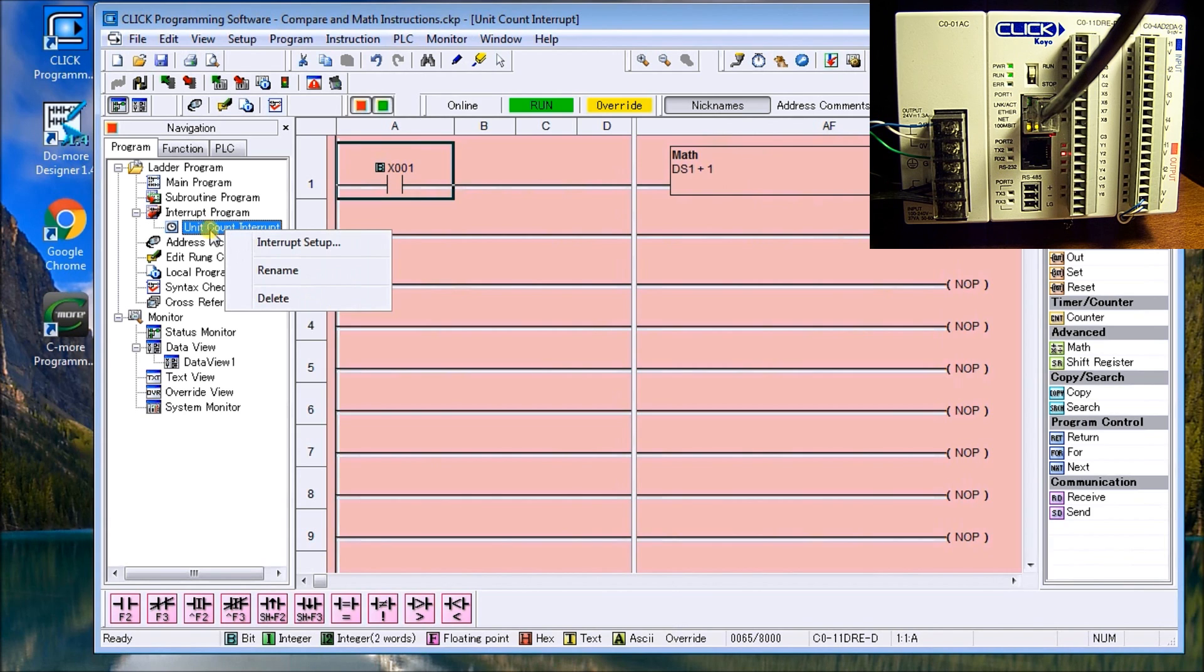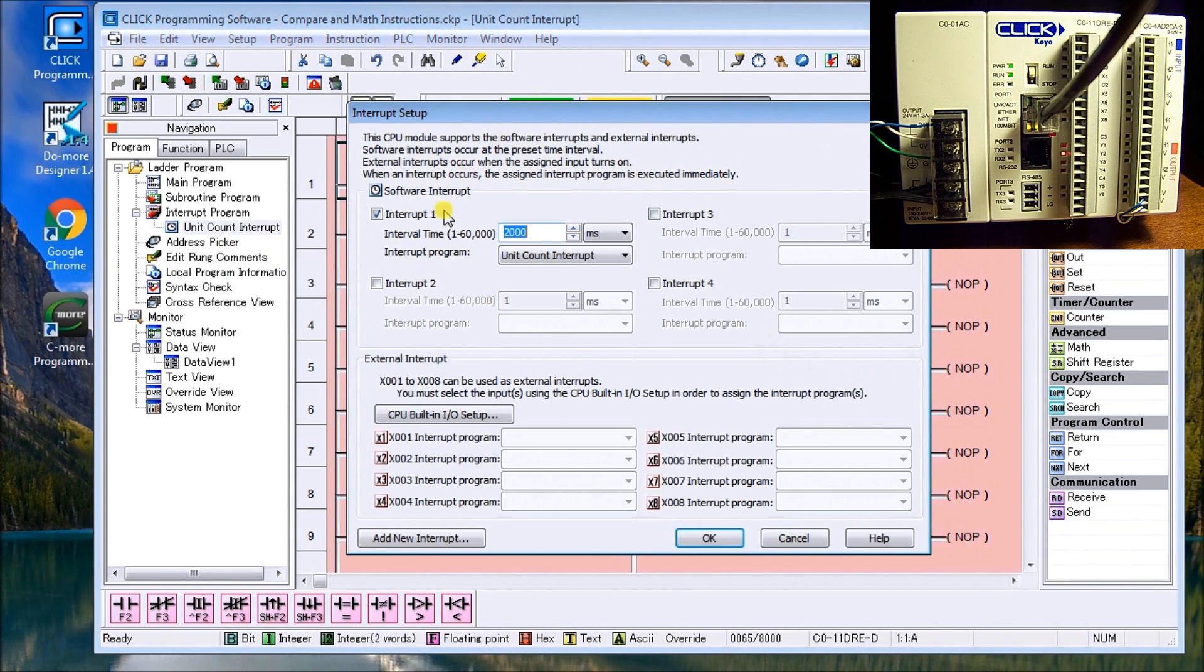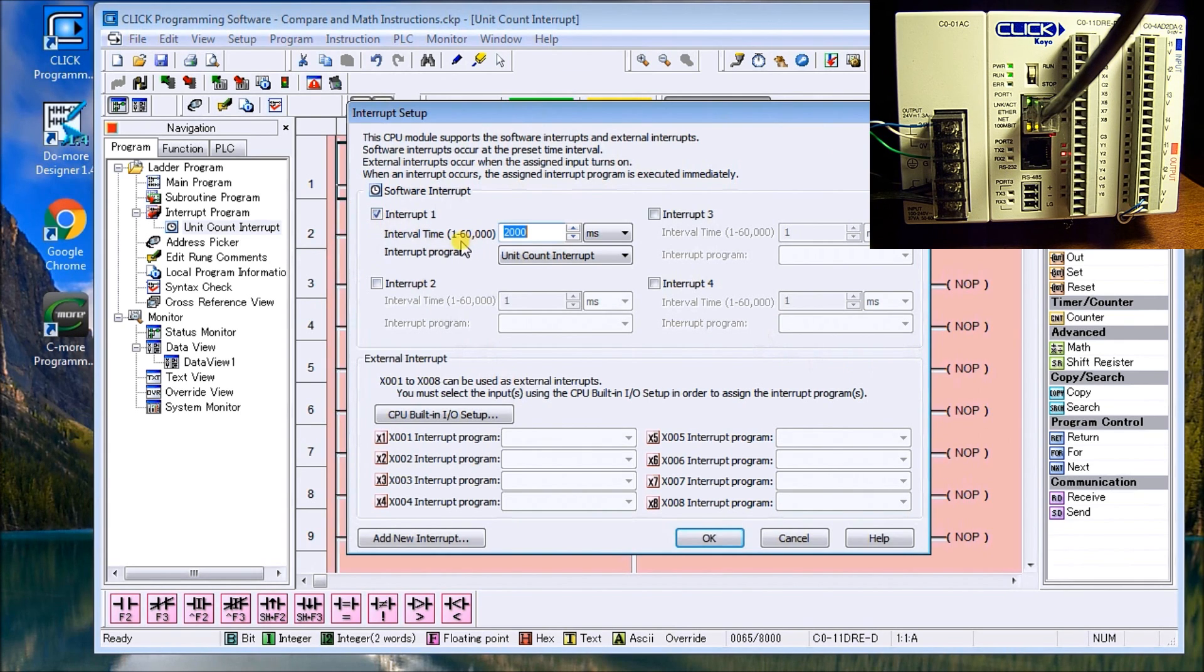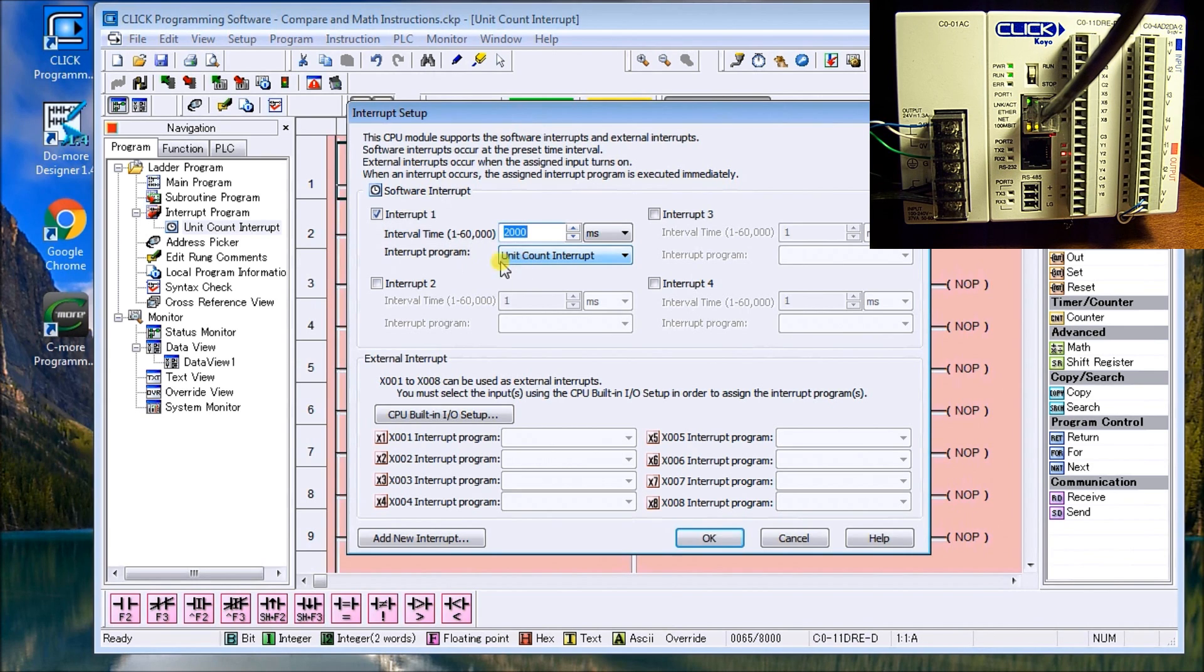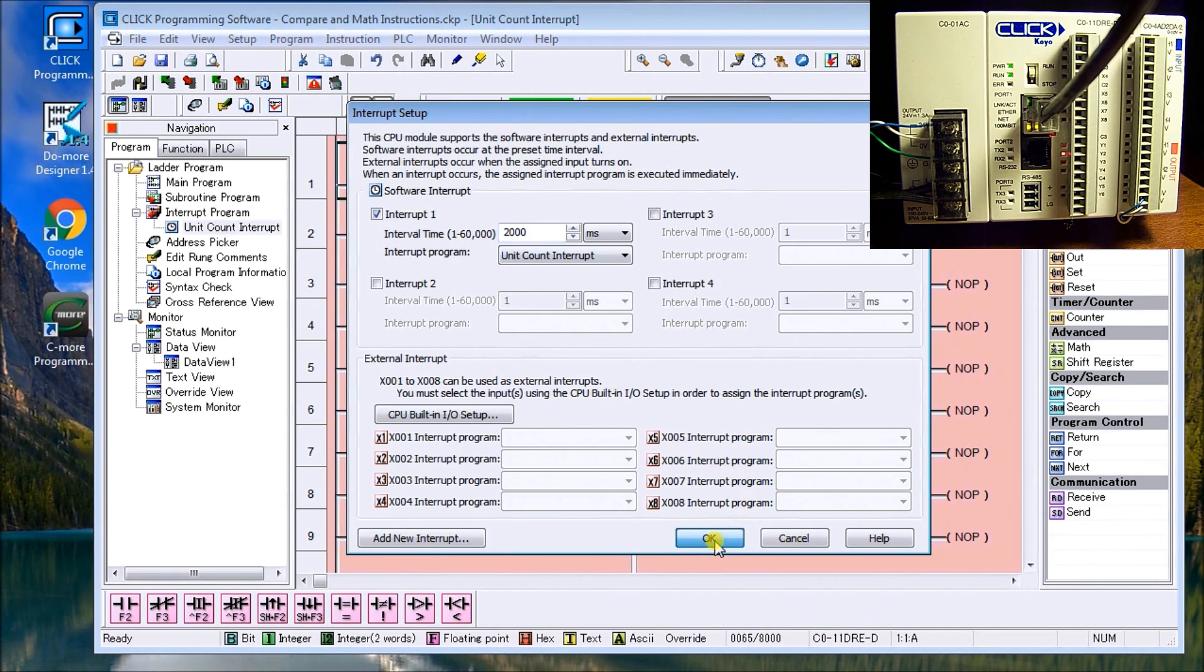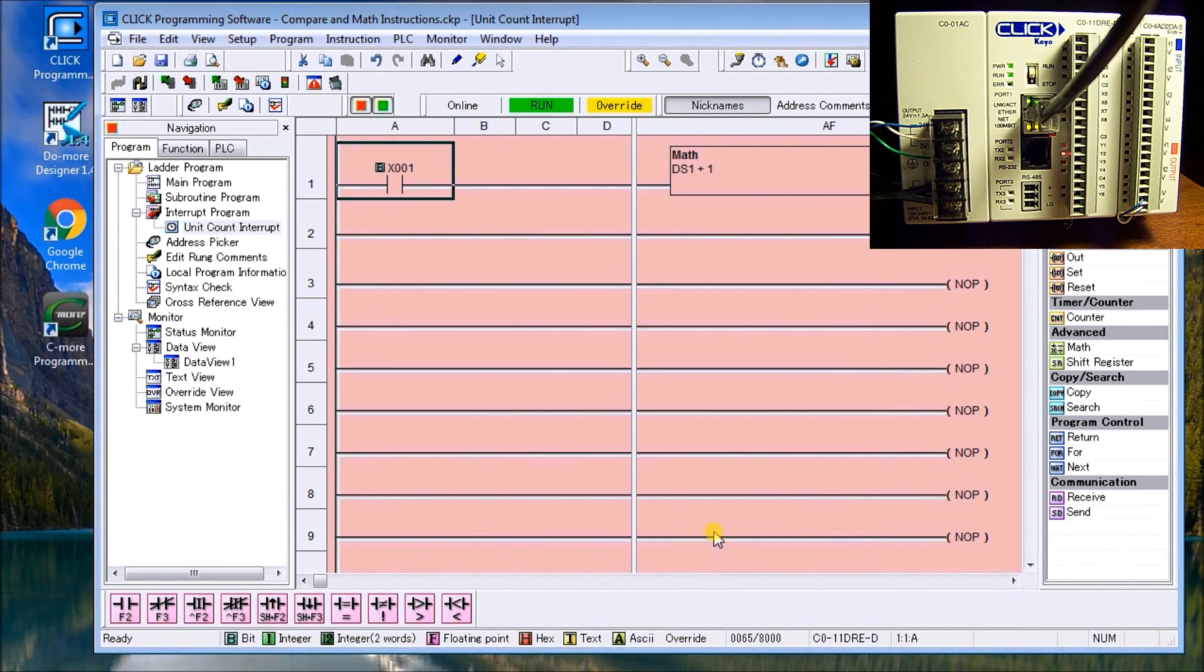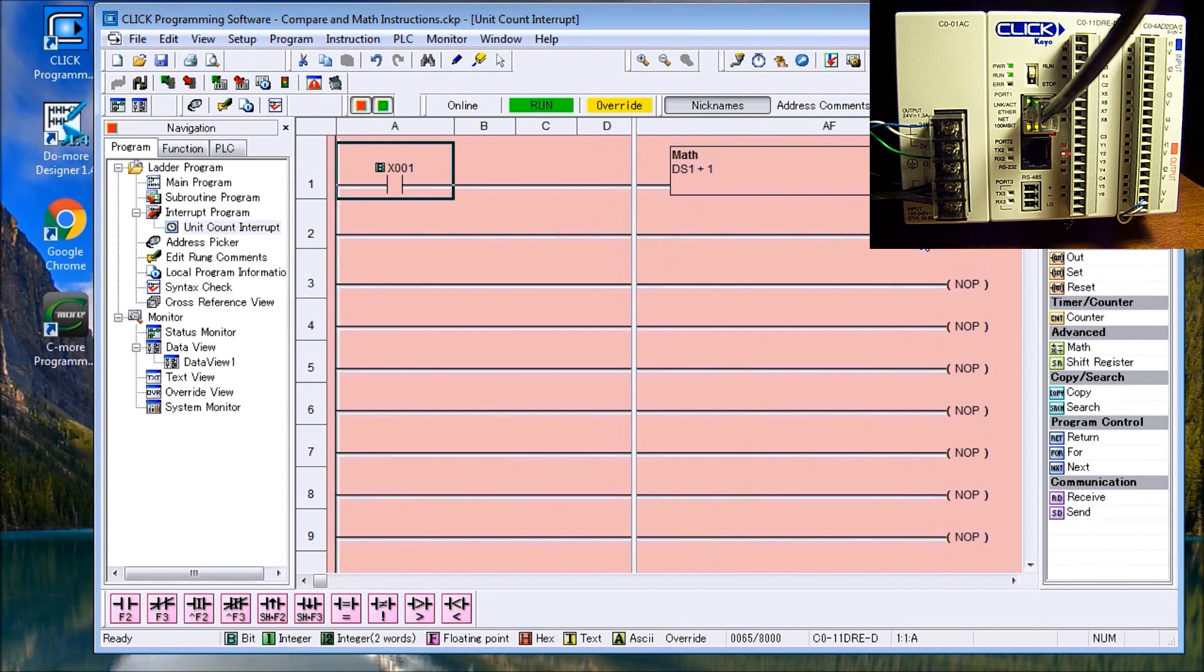Now if I go to the right click and then go to the interrupt setup, I come up with a menu here that I can say turn on interrupt one. I'm going to enter the interval time will be 2000 milliseconds, which would be two seconds. And what it's going to do is call up this unit counter interrupt, which is what we called it here. So let's say okay. And you'll notice that here at the end of every interrupt, there's a return, which then returns to the point in the program where you left off.